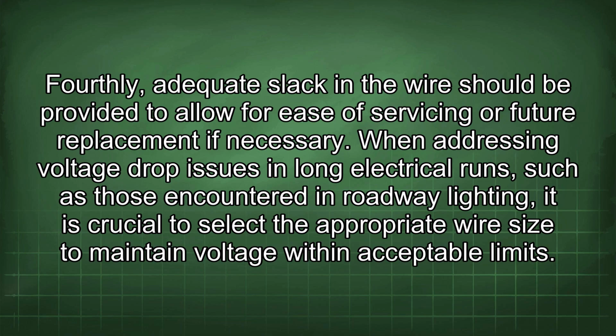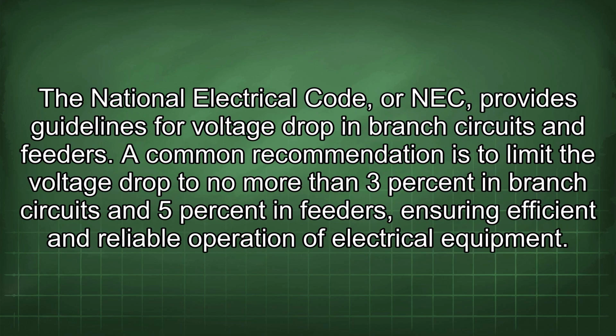When addressing voltage drop issues in long electrical runs, such as those encountered in roadway lighting, it is crucial to select the appropriate wire size to maintain voltage within acceptable limits. The National Electrical Code, or NEC, provides guidelines for voltage drop in branch circuits and feeders. A common recommendation is to limit the voltage drop to no more than 3% in branch circuits and 5% in feeders, ensuring efficient and reliable operation of electrical equipment.